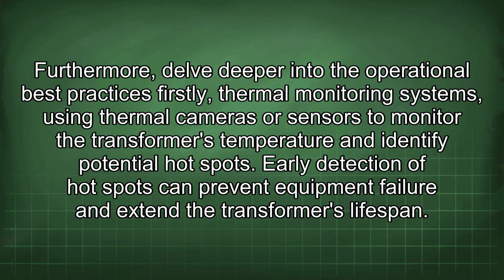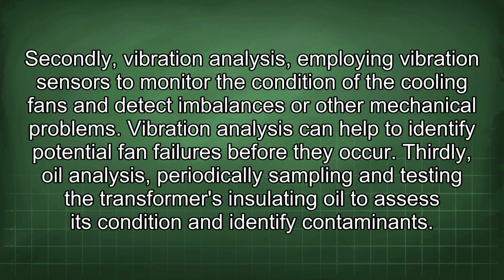Firstly, thermal monitoring systems, using thermal cameras or sensors to monitor the transformer's temperature and identify potential hotspots. Early detection of hotspots can prevent equipment failure and extend the transformer's lifespan. Secondly, vibration analysis, employing vibration sensors to monitor the condition of the cooling fans and detect imbalances or other mechanical problems. Vibration analysis can help to identify potential fan failures before they occur.